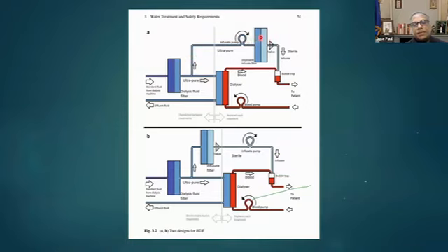This is an infusate pump, and after the infusate pump there is another filter which clears the dialysis solution, and this is directly infused into the patient's blood. The point to be noted is that the solution goes directly into the patient's blood, so the solution should be of extra good quality. The standard of care should be that normally seen in intravenous saline preparations.